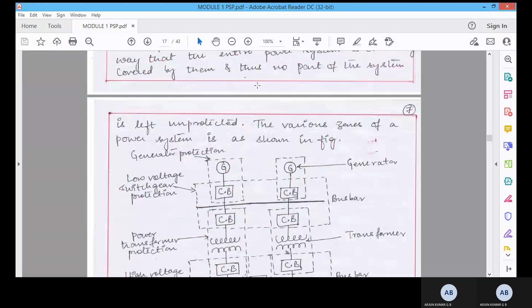Once again, I repeat that. What do you mean by zone protection? See, all the dotted lines, rectangular boxes, each represent one kind of zone. Observe the first zone: there is the generator protection, with the generator and circuit breaker also. Then this rectangular bar represents the bus bar protection, on either side, for the transmission line, the transformer side, as well as the circuit breaker side. We should give protection to both. This is a complete protection for the bus bar.